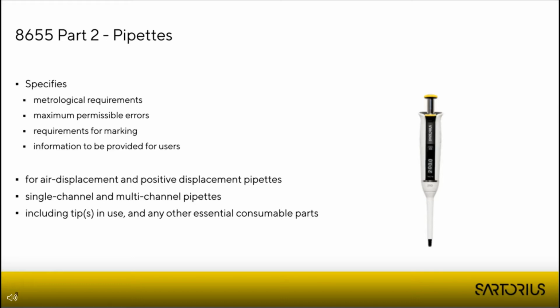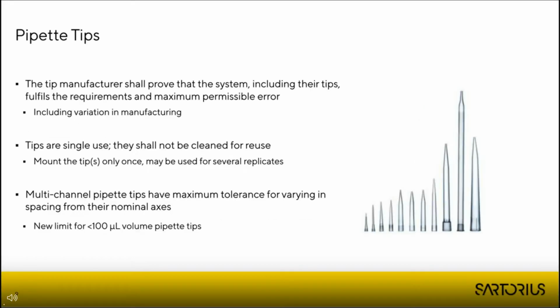This part 2 includes air displacement and positive displacement pipettes, multi-channel and single channel variants, and it always combines the tip and the instrument together. So this is a very important highlight. Let's go to the tips. So what actually changed between the first revision and the second revision is that in the second revision, the language concerning tips is much more strict.